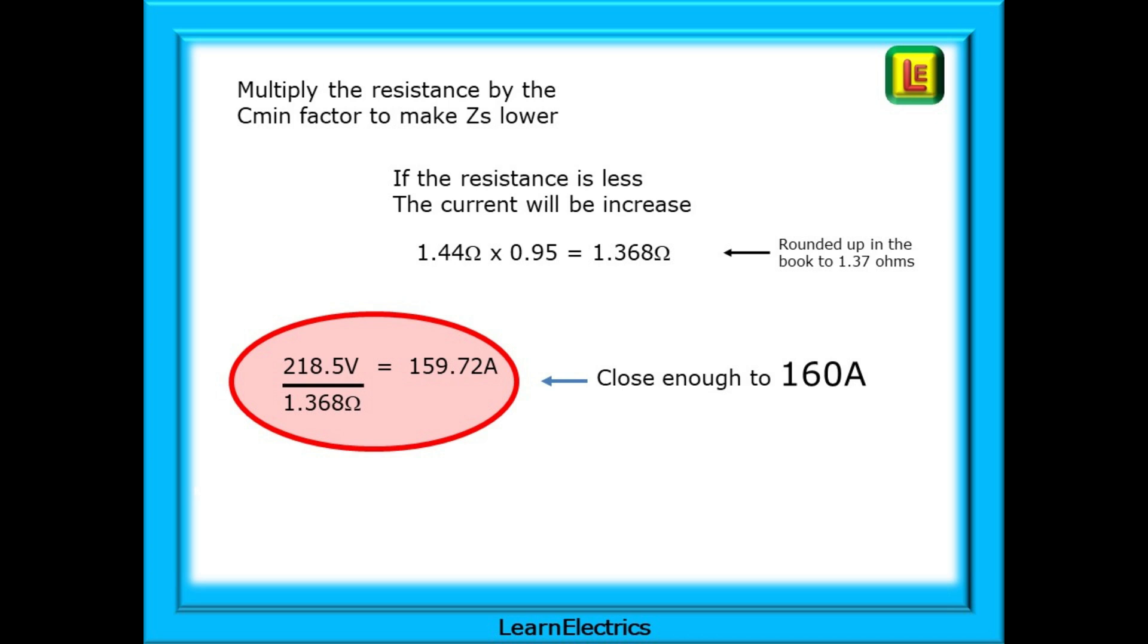What we do is multiply the standard resistance, the raw data, by the same Cmin factor of 0.95. This will reduce the resistance. It will make the maximum ZS smaller. If the resistance goes down the current will go up. 1.44 ohms multiplied by 0.95 gives us a tabulated ZS of 1.368 ohms shown as 1.37 in the book. How does this affect the current? 218.5 volts divided by 1.368 ohms is 159.72 amps which is 160 amps when rounded up.